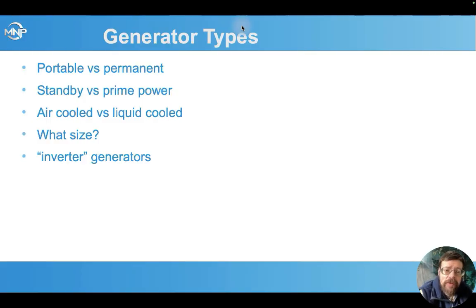When looking at generators, we also start looking at standby versus prime power generators. Standby is generally what we're using until we start getting into the 30-40 kilowatts or larger. There are some smaller prime power generators. Standby is generally intended for backup power for the grid, versus prime power, which is designed to run 24 hours a day for a complete off-grid generator powered situation. Standby tend to be lighter built, lower runtime before they need rebuilding, and just really not as heavy duty. And this has some limitations when we're using them for battery charging, which is a lot heavier load than typical backup power for a house is.